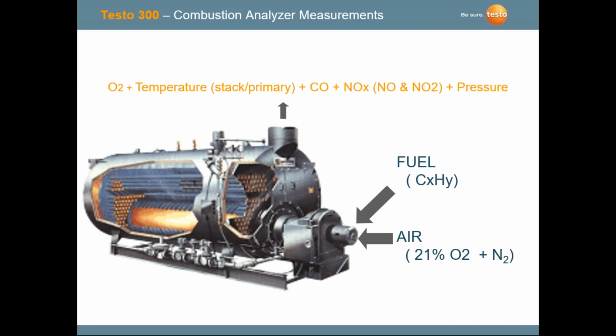In the 300, for instance, we measure NO, which is 95% of the total NOx. And we factor in, and you can adjust this, preset this factor to anywhere you want, from 3%, 5%, 7% on the NO2. So we're measuring NO and we're factoring in the NO2. And again, remember that NO2 is a small percentage, 5% or less, of the total NOx.